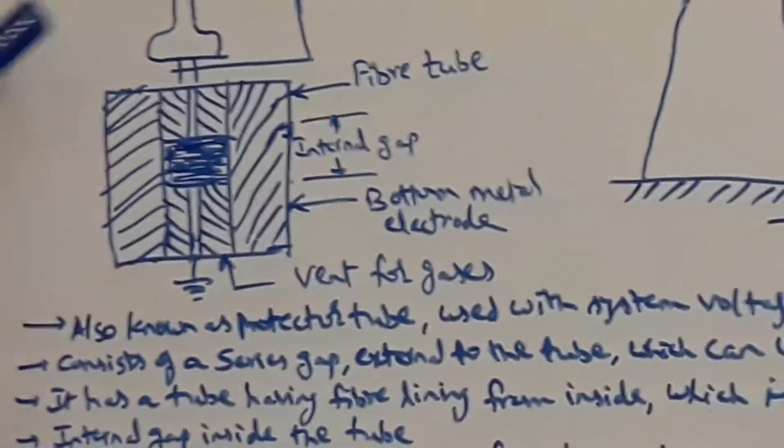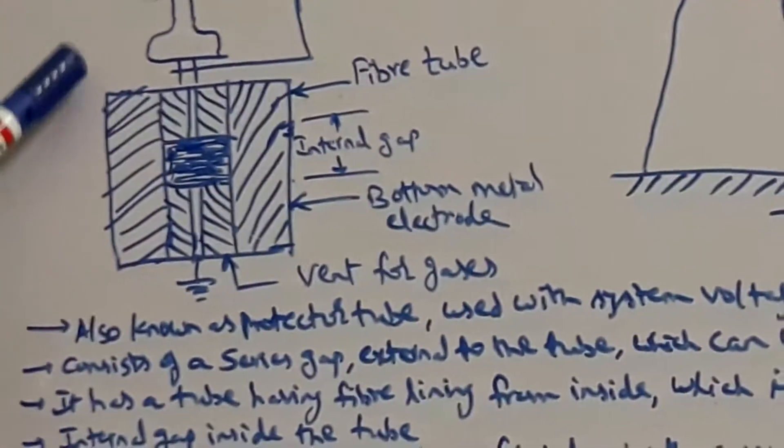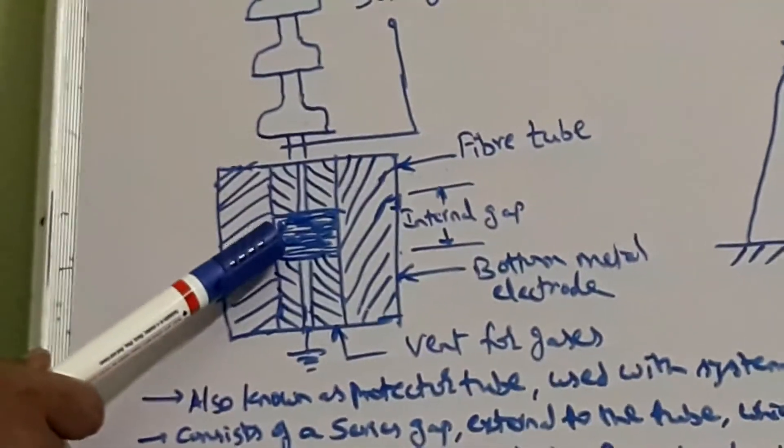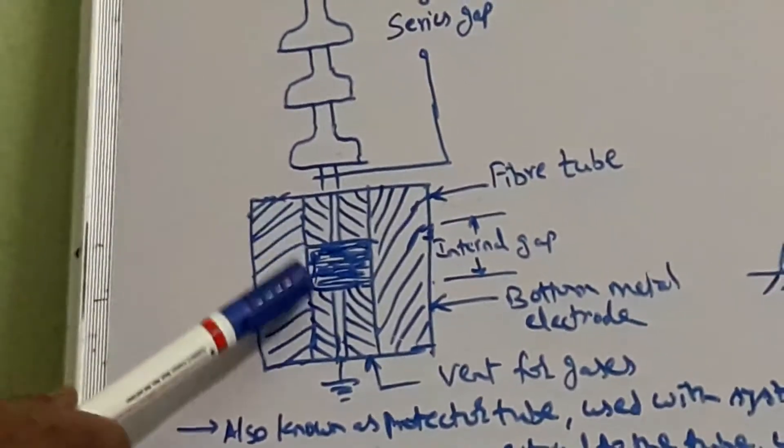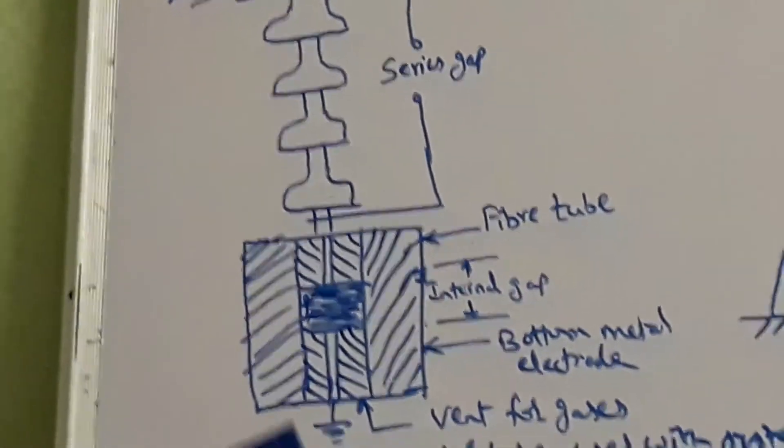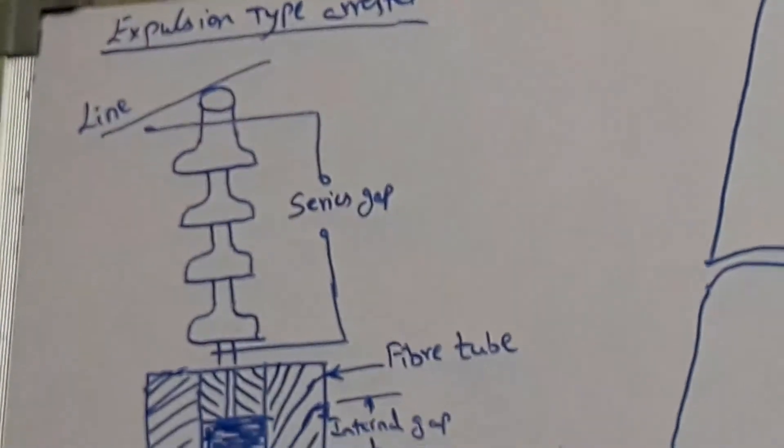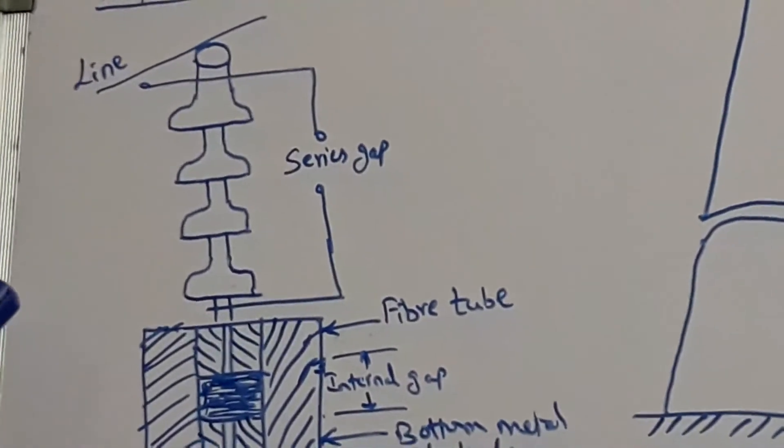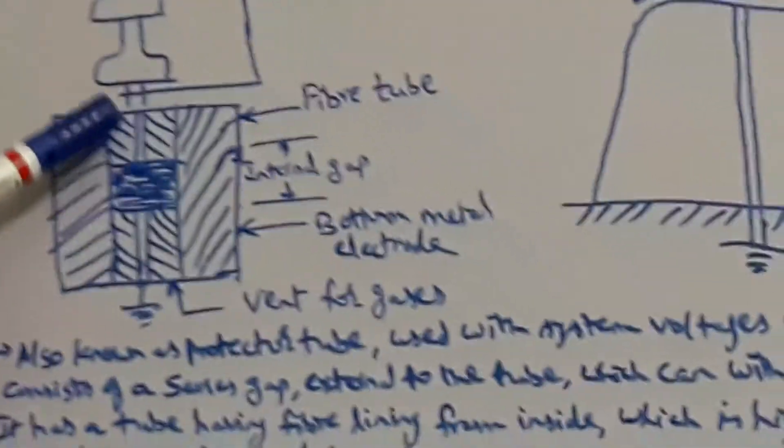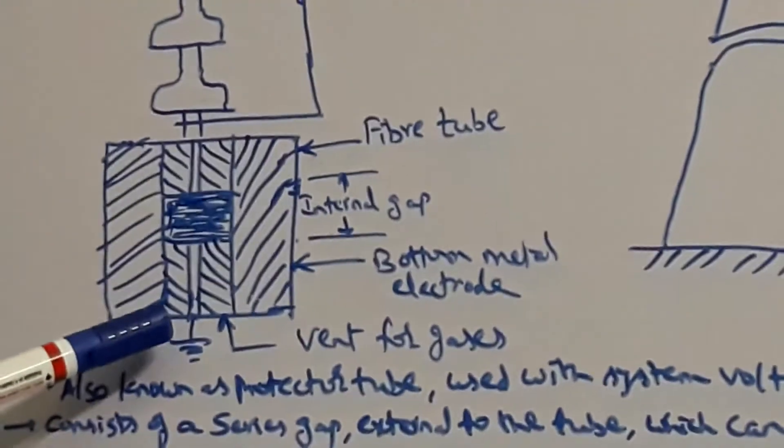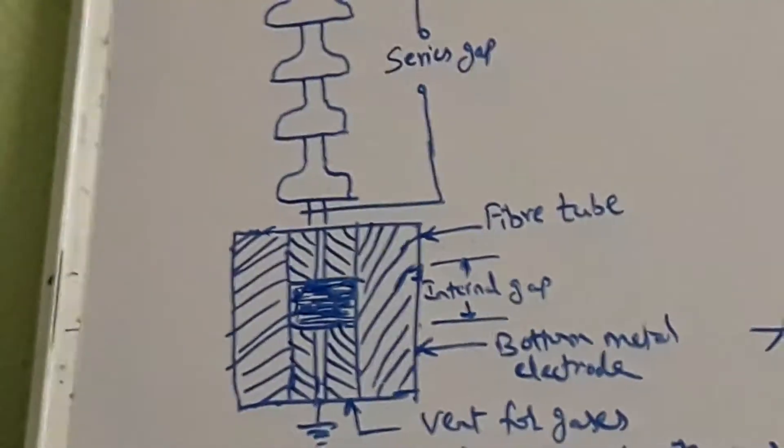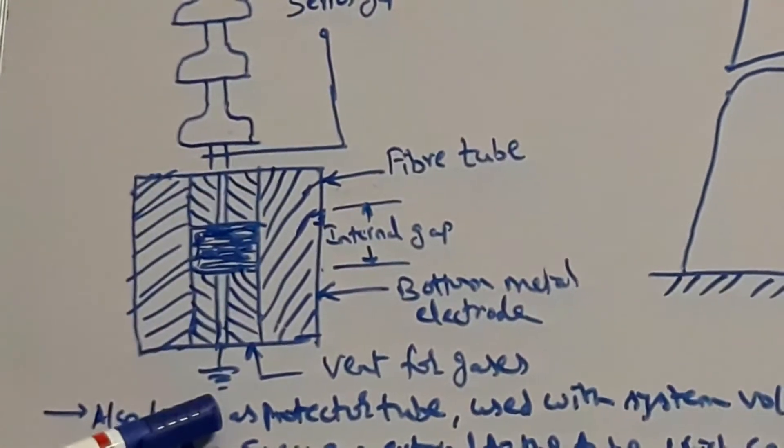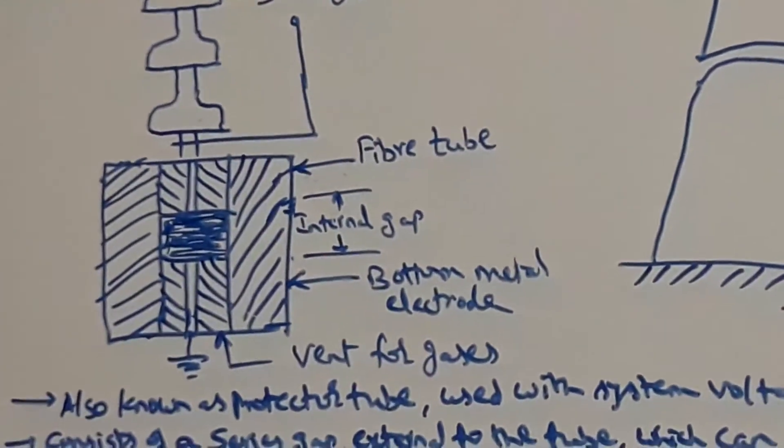The breakdown voltage of the tube should be less than the breakdown voltage of the insulation for which it is used. When an overvoltage occurs, there is a breakdown in the series gap and an arc forms between the two electrodes in the fiber tube, providing a low impedance path for the lightning current to earth. Heat is produced by the arc.